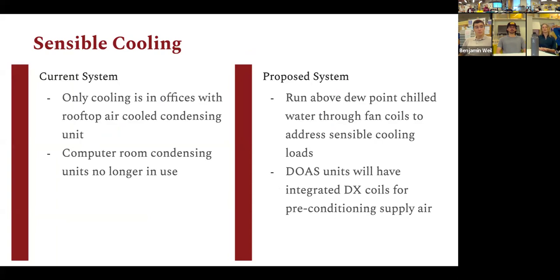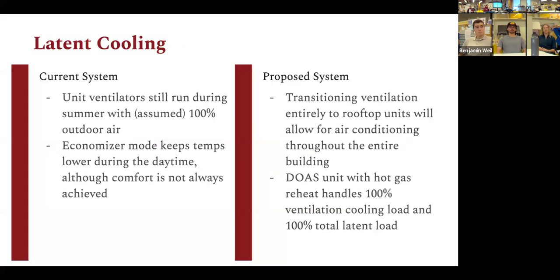What we're proposing to do is to run above dew point chilled water through the fan coils to address the cooling loads and have the DOAS units with the DX coils for the preconditioning of fresh air. To address the latent cooling, the current system uses the unit ventilators, which run during the summer with assumed 100% outdoor air in economizer mode, which allows for the temperature to be decreased during the daytime, but all the comfort levels are not always achieved.